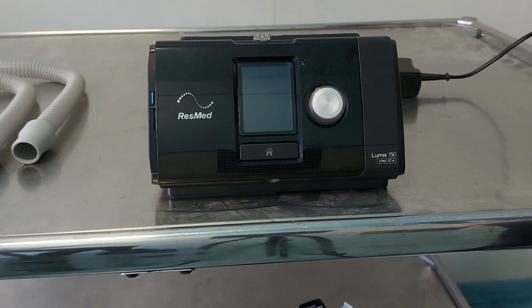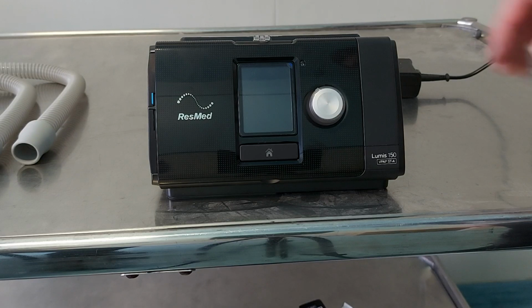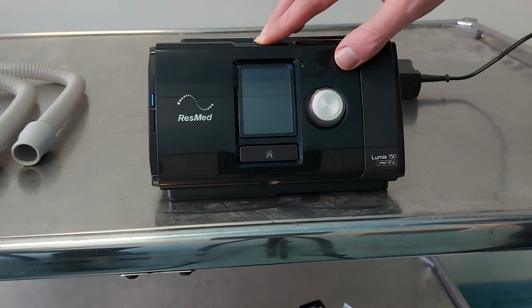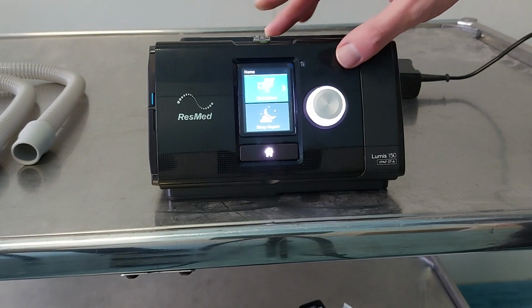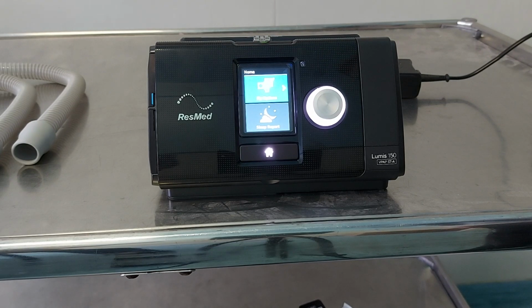Now the machine can be turned on. Always turn the machine on before turning the oxygen on, and turn them off in the reversed order. Oxygen off first, then the machine. This is to prevent the oxygen from building up in the machine and to reduce the risk of fire.